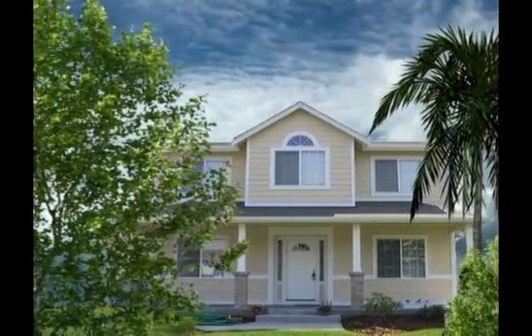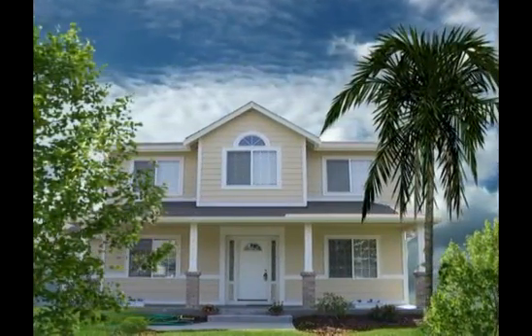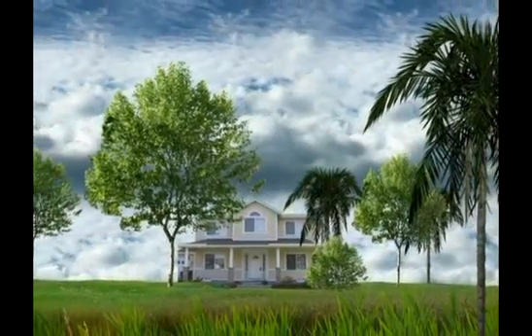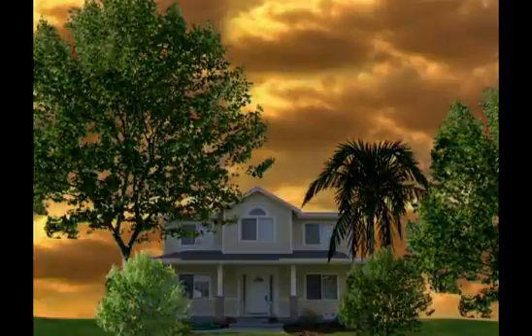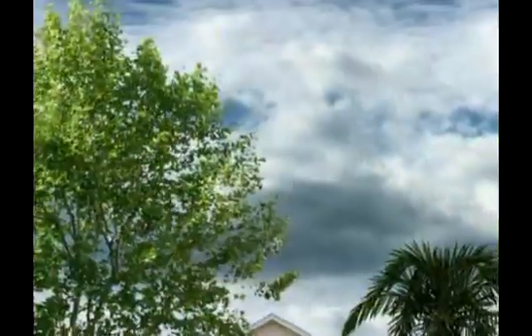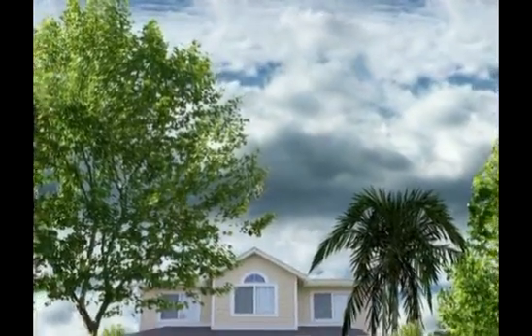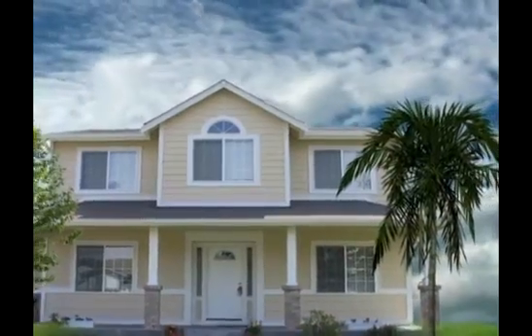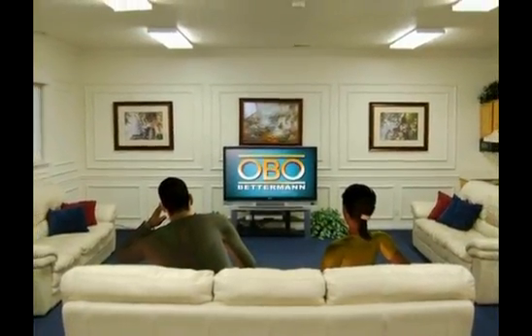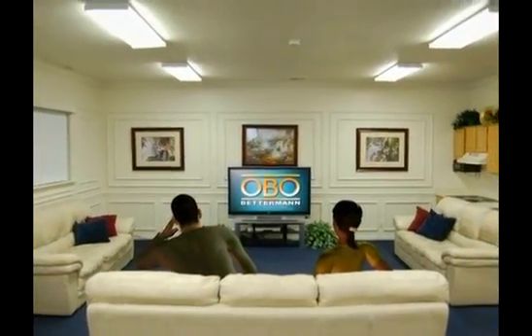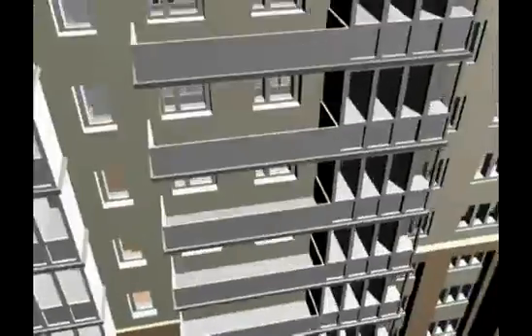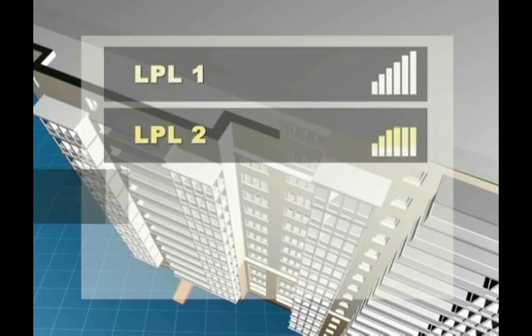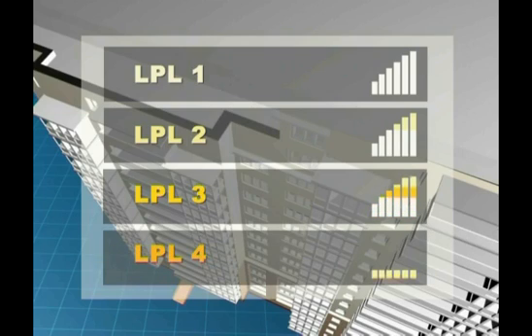Before employing a lightning conductor, the prospective buildings and geographical areas need to be carefully surveyed for the number of times the area is struck by lightning, the trees and tall structures near the building, the area of the building, the number of people living or being employed in the building, and the value of electrical and electronic appliances inside the building. The IEC recommends four levels of protection based on these factors, from the high level LPL-1 to the normal LPL-4 level.